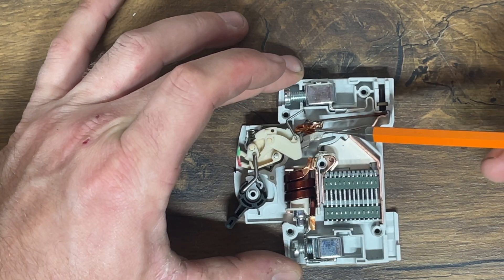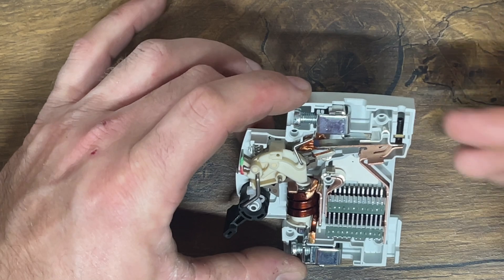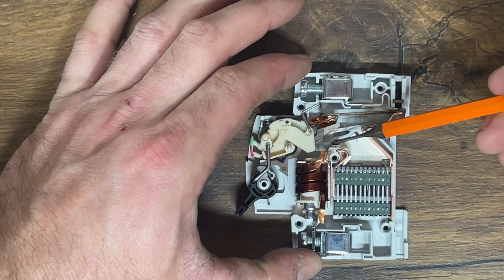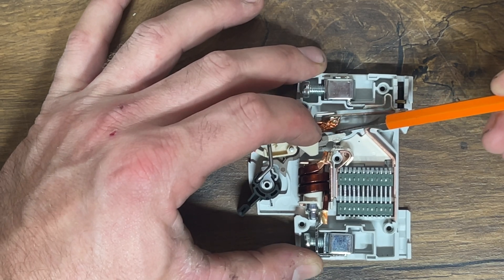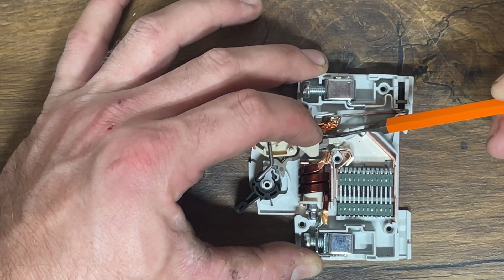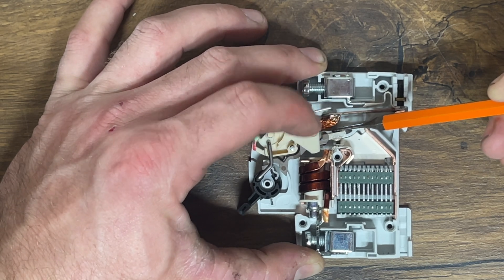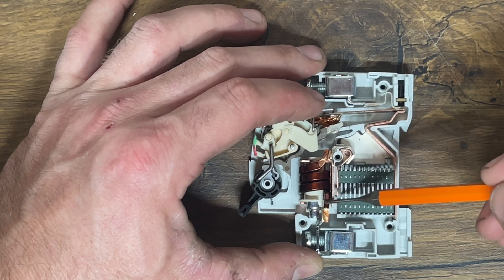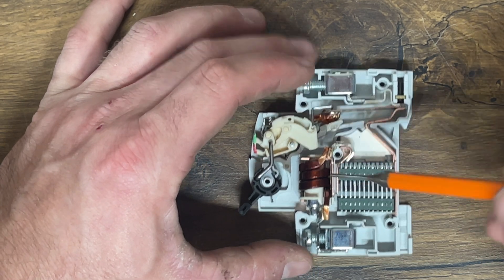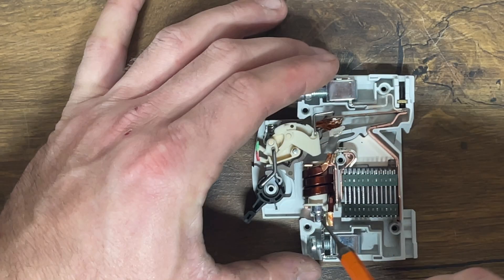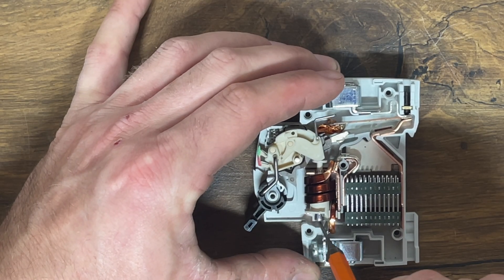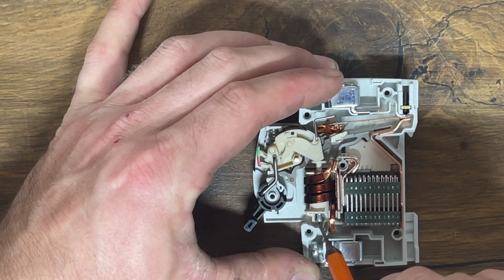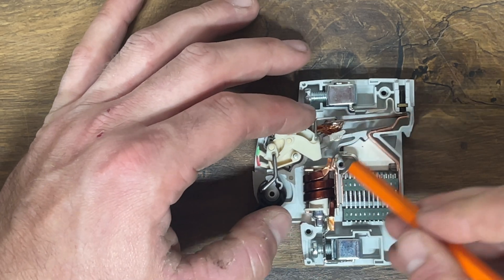We then have our two contacts, of which one is connected to our bimetallic strip with a braided copper wire. There's quite a small gap between these contacts, but it doesn't take much for this trip device to operate. It's almost on the brink of wanting to flick and disconnect at any one time. But when you've got that bimetallic strip, all it takes is for that to bend enough to pull that mechanism over and break that connection, or for the solenoid to push it from above, which shows you how both parts of those mechanisms work in order to flick that contact away from the other one.